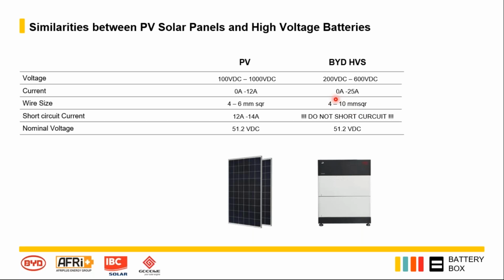Also, we'd recommend when using cable not to use your house wire, because your house wire typically is only rated about 600 volts. If you use your solar cable, it's typically double insulated and more suitable to the application. With regards to your short circuit current, this is the main difference between your photovoltaic cells and your BYD batteries. Your short circuit current on your PV panels is between 12 and 14 amps, and please don't short circuit your batteries. When the battery turns on, it does a quick self-check, and it checks if there's any shorts in the system, and it won't turn on if it detects any shorts. But if there is a short while it's operating, it will damage the battery. And the nominal voltage, unfortunately, is incorrect there. I'll change that before the slide goes out.